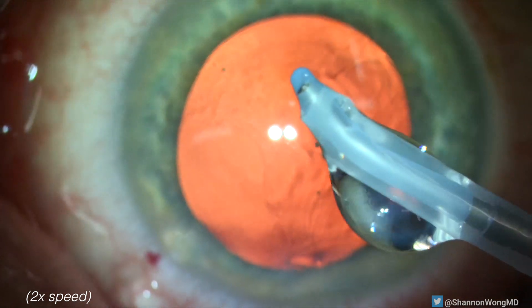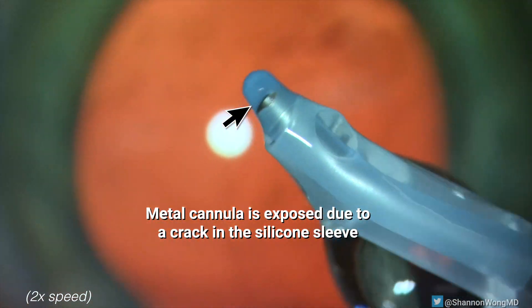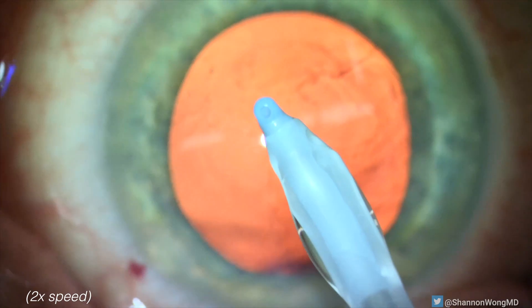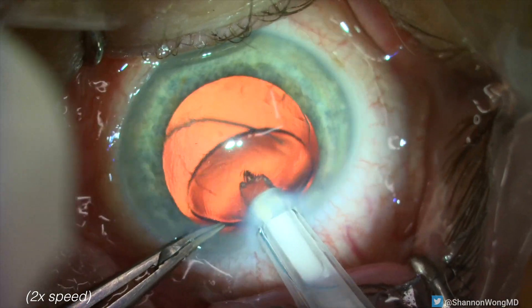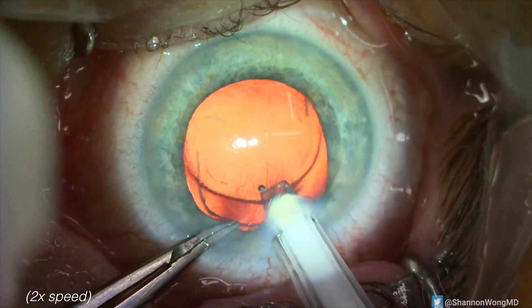How does this happen? When we rotate the IA tip to inspect the posterior surface — that is on the opposite side as the aspiration port — we see a crack in the silicone tip and the metallic internal core.